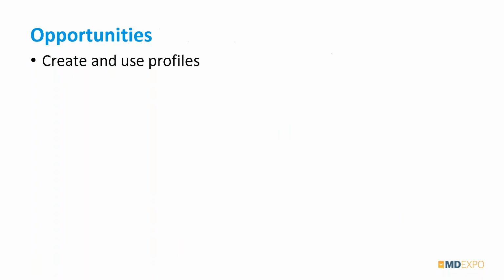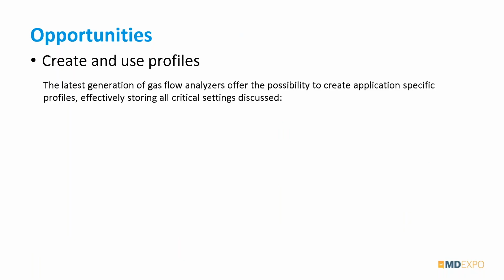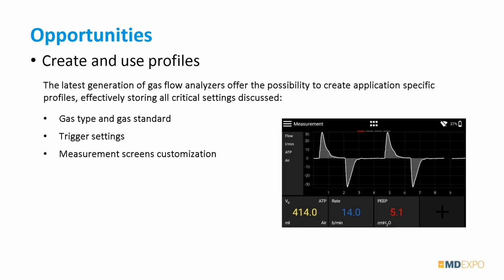So what are the opportunities offered by modern gas flow analyzers? One important thing, if your gas flow analyzer offers that feature, we highly recommend you create profiles. Many gas flow analyzers out there allow you to save all your settings for a specific device you figured out, maybe by testing or by looking at the manual, as profiles. Typically profiles include gas type, gas standard, trigger settings, and all your measurement screens. For example, here you can see an example of a measurement screen. Sometimes you can arrange them differently, you can colorize them differently, and all these settings can go into a profile. So you can have a profile, for example, for ventilator A and a different profile for ventilator B. Each time you have the same application again, instead of going through all the settings again, you just load that profile and it sets it up correctly for you. This really helps reduce the risk of inappropriate settings and reading errors at the end of the day.